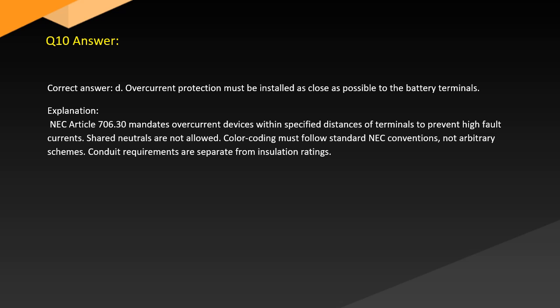Answer. Correct answer: D. Overcurrent protection must be installed as close as possible to the battery terminals. Explanation. NEC Article 706.30 mandates overcurrent devices within specified distances of terminals to prevent high fault currents. Shared neutrals are not allowed. Color coding must follow standard NEC conventions, not arbitrary schemes. Conduit requirements are separate from insulation ratings.